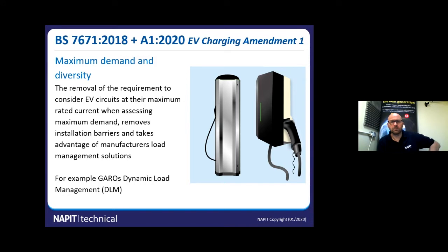Now, the great thing with that type of system that we've developed is that as homes move away from diesel or petrol cars to have two EVs, we can then add a second EV point as well. And we can load manage up to 32 charge points. And I appreciate that won't be on the standard home. But when we look at the commercial markets and what's happening there, there's maybe 25, 30. We've done some applications with 100 charge points on an apartment block or on a large car parking space. We can then load manage circuits up to maybe 600 amps 3-phase and give a solution where it will automatically change the load as the load in the building changes. It's a massive benefit, especially with the fact that we've got limited supply in our buildings at the moment.